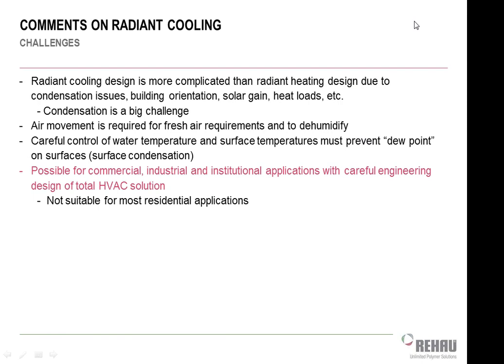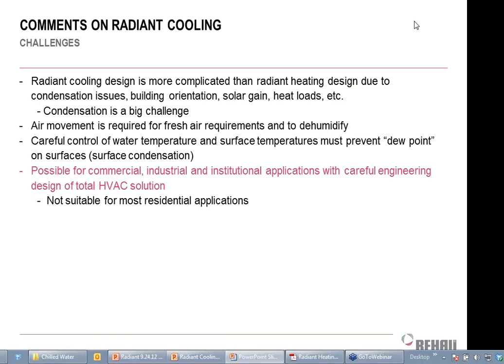I'll also put controls on this system to make sure that I don't send water around the building that is cooler than the current dew point. But if I do that, I don't have any way to dehumidify the air, right? Because with a normal cooling airside system, I am doing both sensible and latent energy. If I have a radiant cooling system, it's sensible only. It cannot do any latent cooling, because if it does, once again, I'll have condensation on the floor, which won't be good. So I still have to have a separate latent system, which usually can be doubled up with my ventilation system. So I'll typically have a 100% outside air ventilation air handler that's doing 100% of my space latent load as well.